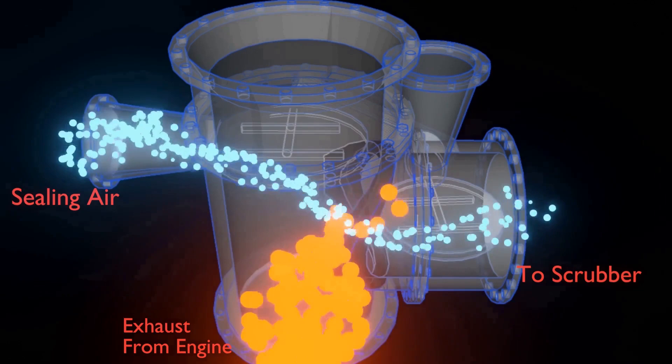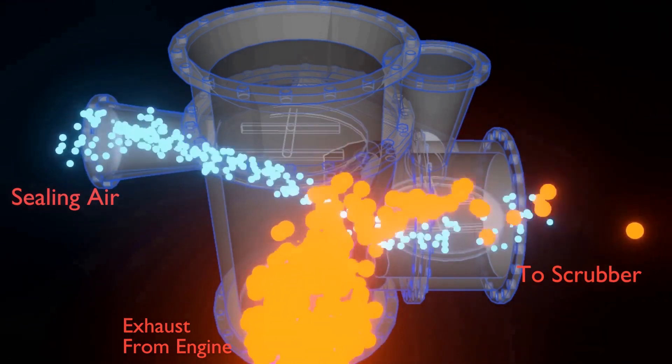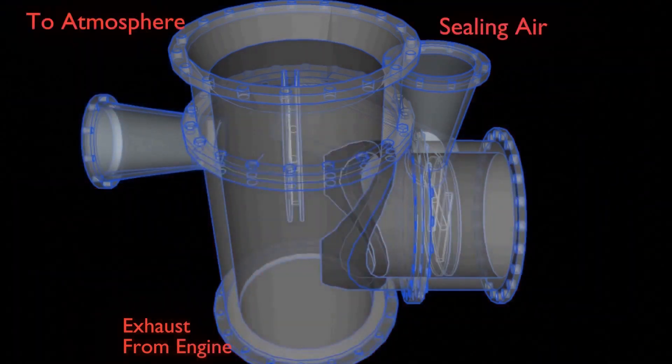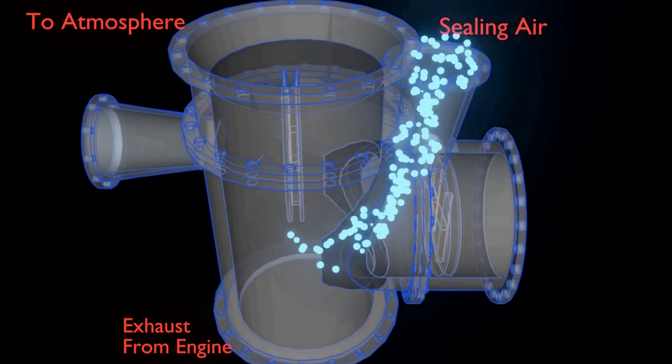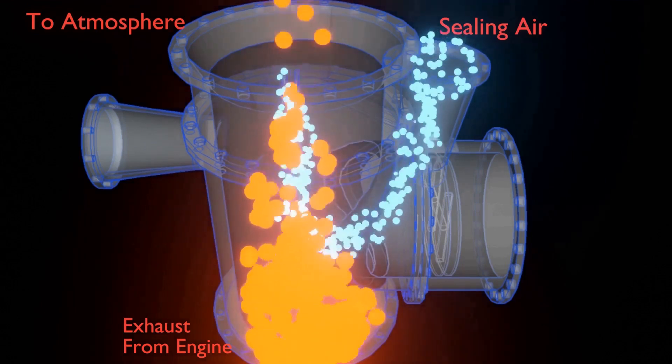Bypass damper valves will be opened instantly to bypass position in case of the following: 1. Scrubber shutdown initiated by instrumented safety function. 2. Emergency stop is activated. 3. Loss of instrument air or controller signal.